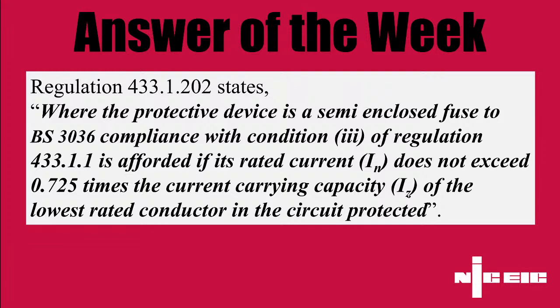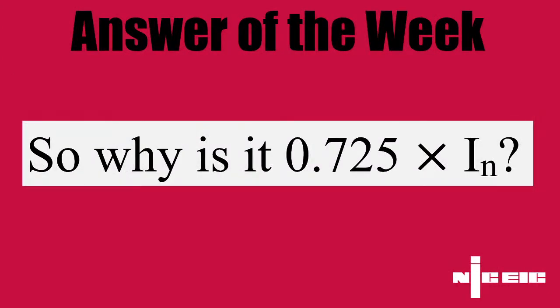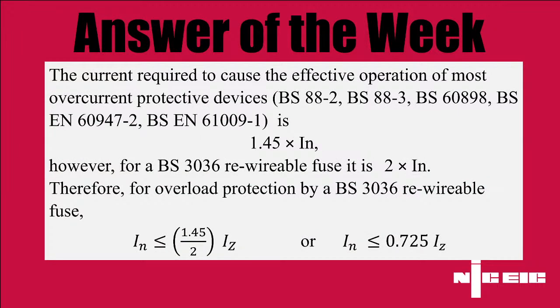Why do we think it's 0.725? Really that's to do with the fact that BS 3036 fuses are a little bit different from most of the other overcurrent protective devices. If we look at most of the overcurrent protective devices, so BS 88 type fuses, 60898 circuit breakers, and also 60947-2 circuit breakers, 61009 RCBOs, all of those have got a value of 1.45 times the In, because all of those types of protective devices, the effective current to result in operation of those devices, or as it's referred to, the current required to cause effective operation, is based on 1.45 times the rated value.